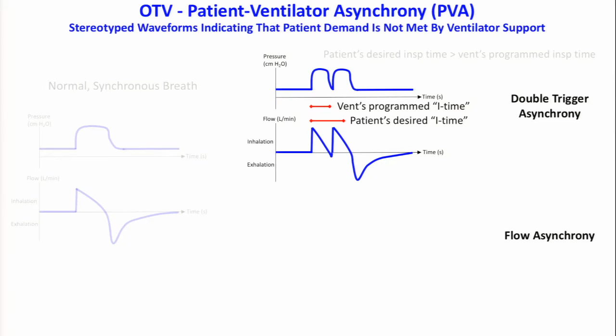Flow asynchrony, which is something I've done a lot of simulation work on and is frankly really miserable, occurs when the patient's flow demand is greater than the vent's flow supply. So in one of the most common modes of mechanical ventilation that we use, something called volume control, the ventilator actually has a programmed slope of flow delivery. So the morphology of that inspiratory flow curve is actually completely set by software, and it's inflexible. So if a patient wants significantly more flow than is set by the ventilator, the patient doesn't get it.